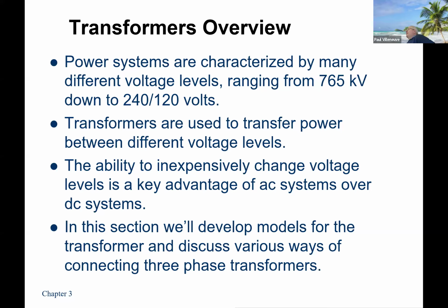And why do we do that? Because of that third bullet right there, the ability to inexpensively, maybe we can even use another word, cheaply, change voltage levels from a higher level to a lower level or vice versa, right? It can go bi-directionally, although there are some challenges and we'll talk a little bit more about it. Over the summer, I went to a conference and they're talking about this bi-directionality. Some of the transformer manufacturers may not necessarily be designing them so that they are truly bi-directional. But for our intents and purposes in our class, we'll focus on them being bi-directional, the power devices.